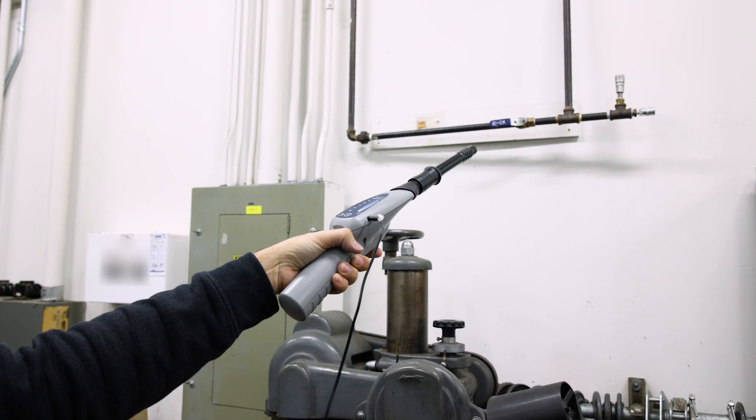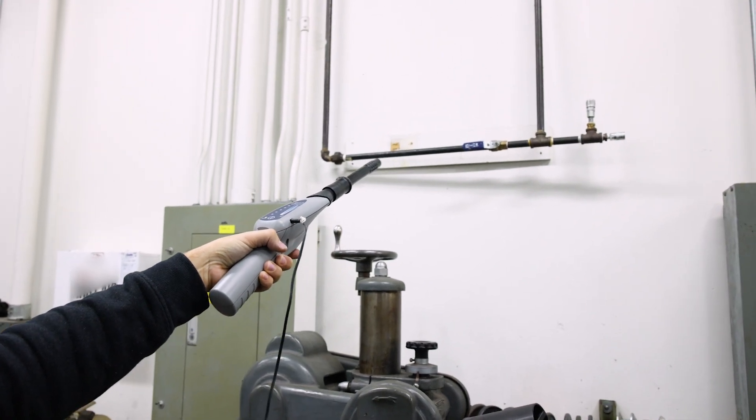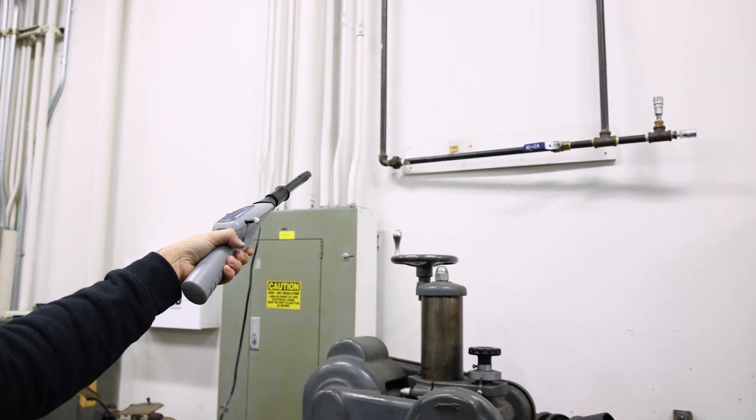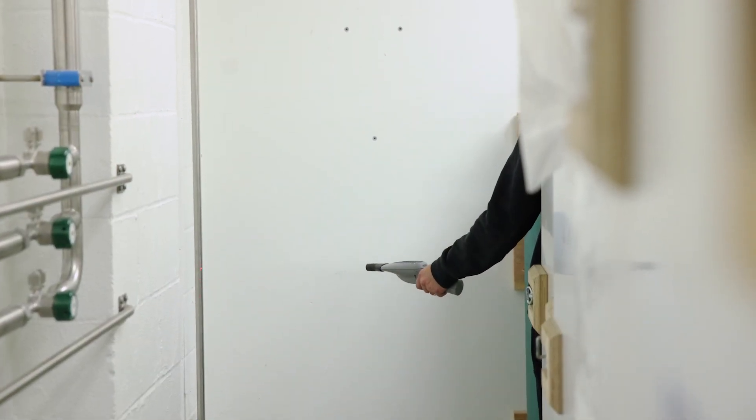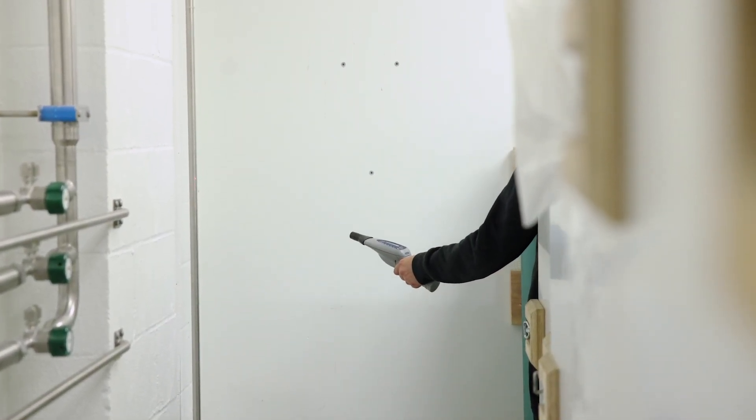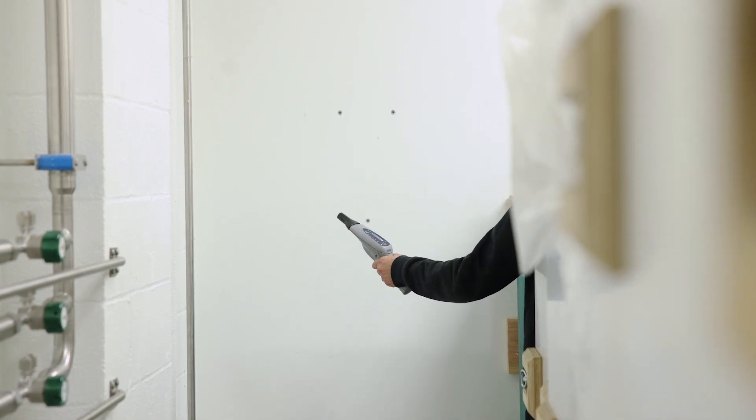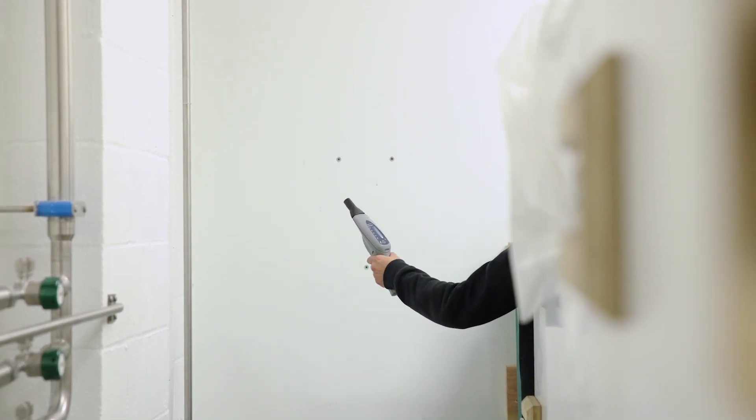Whisper can be used to locate malfunctioning steam traps and leaks in compressed air systems. It can even detect nitrogen that is often used to pressurize systems during install, making it the only leak checking technology that can be used for nitrogen.